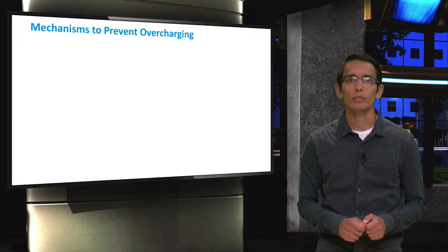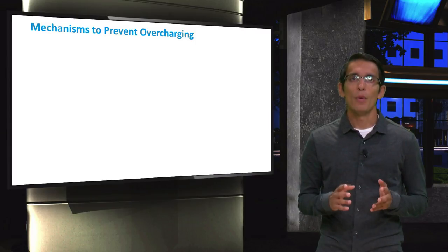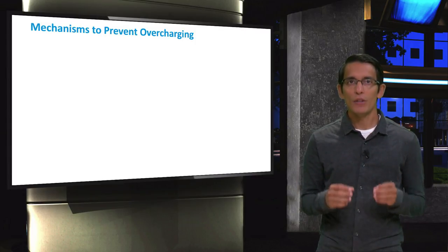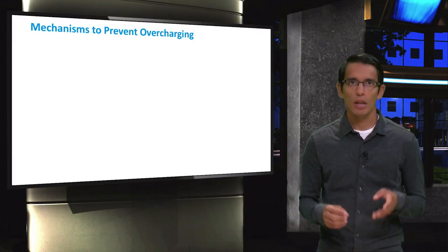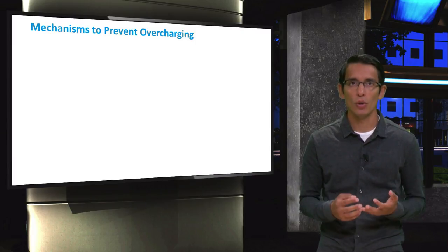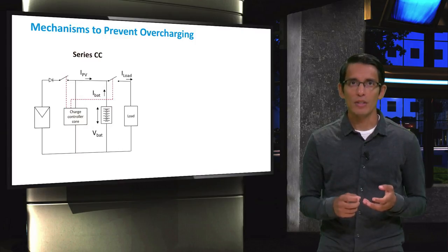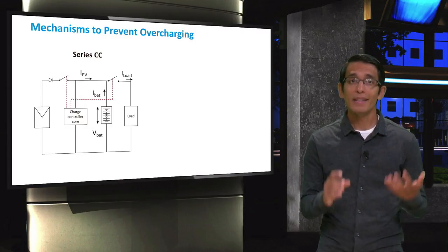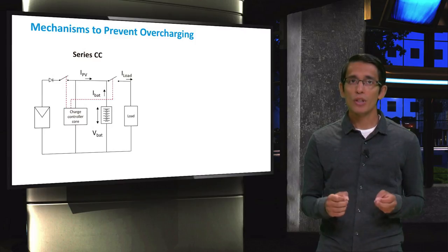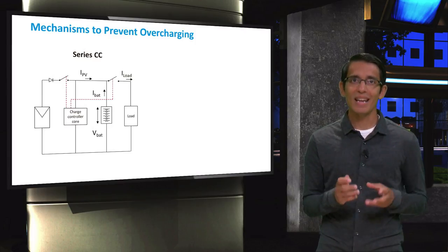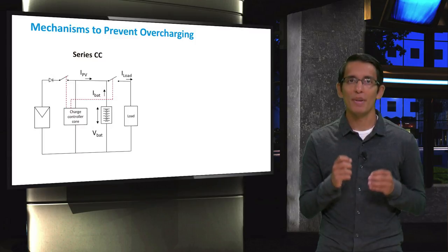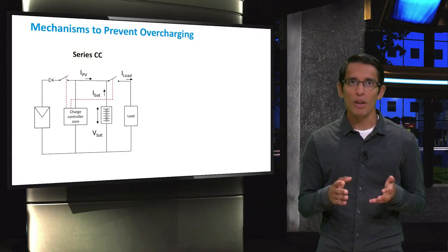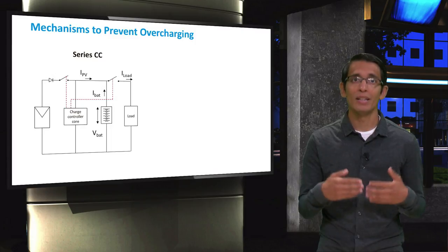Now that you know that a charge controller is meant to protect a battery in various ways, let's take a look at a few ways that this can be accomplished. You just saw that one of the main functions of the charge controller is to prevent overcharging of the batteries. There are two ways this can be achieved inside the charge controller. The first method is called the series charge controller. In a series charge controller, overcharging is prevented by disconnecting the PV array until a particular voltage drop is detected, at which point the array is connected to the battery again and charging can continue.